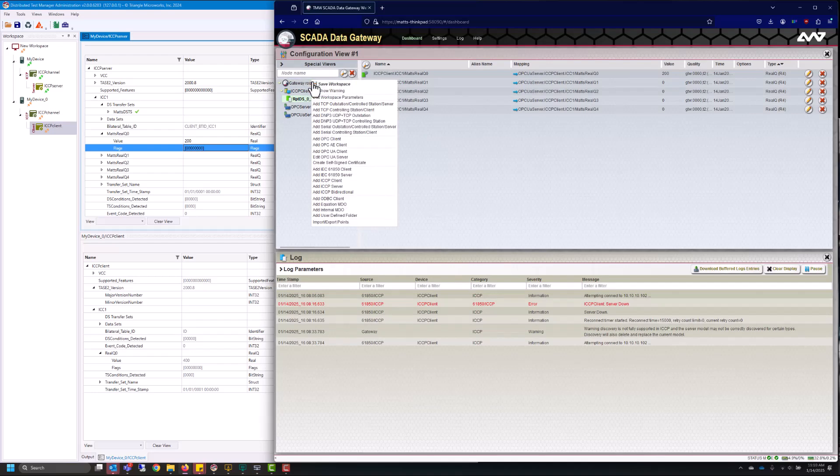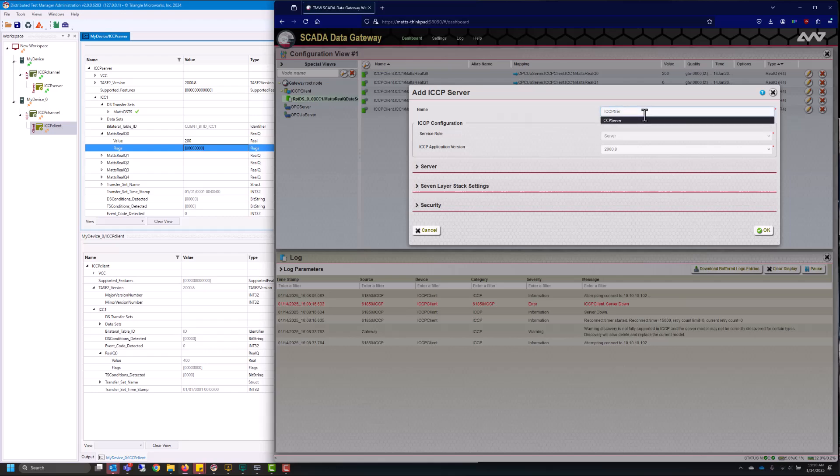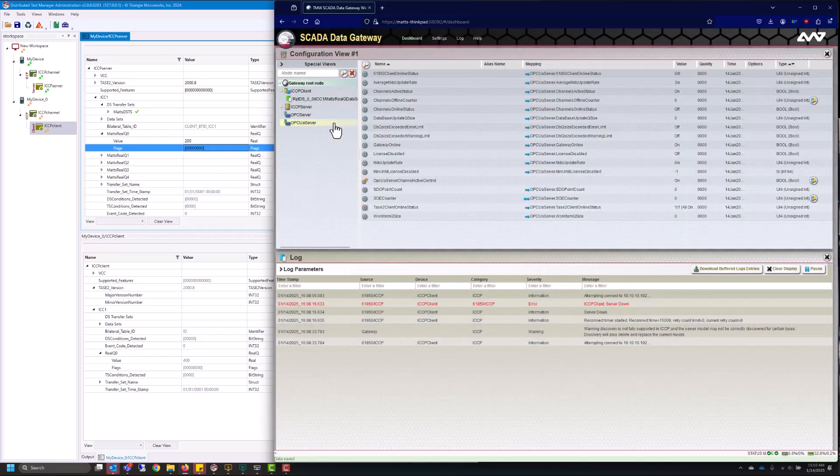To do that I will right click and I'll go down to add an ICCP server. I'll give this a custom name as well. Go down to the server settings and this is my server setting which is on my gateway so that's 10.10.10.106 and then I'll go ahead and hit OK.